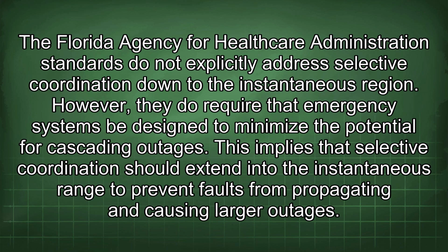The Florida Agency for Healthcare Administration standards do not explicitly address selective coordination down to the instantaneous region. However, they do require that emergency systems be designed to minimize the potential for cascading outages. This implies that selective coordination should extend into the instantaneous range to prevent faults from propagating and causing larger outages.